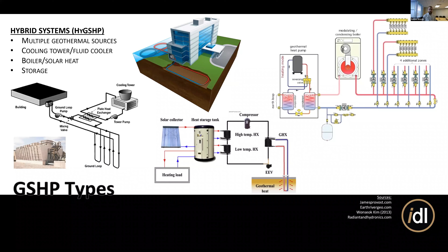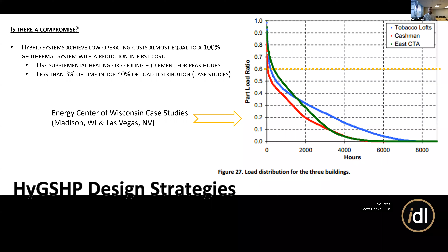But if you look at 8,760 hours in the year, if we look at sizing our system to meet just say 60% of our peak, then the amount of equipment we have to install is going to be much smaller. And less than 3% of the time of the year will we be relying on that worst case scenario. And that's where we can upsize some of that supplemental equipment. So how do we figure out where to draw the line?